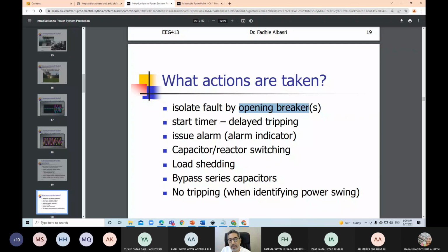Sometimes the action is not immediately taken. It takes a time delay first: I wait before I take action. Sometimes I take it immediately. Sometimes I give an alarm if the parameters are not too high. Okay, I give an alarm that there is an indication. This is not urgent, but it gives an alarm that there's an abnormal situation that needs to be taken care of before it evolves to a dangerous situation.